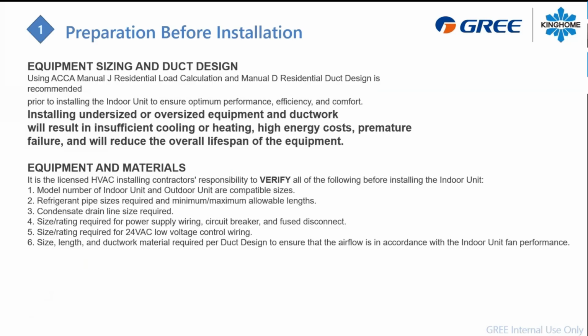So first things first, every time you do a job, make sure your ductwork and the equipment are compatible with your load calculation. This is according to the ACCA Manual J residential load calculation. You need to match a good load calculation from the house you're about to install the unit in. If it's undersized or oversized, it will not be efficient enough in cooling or in heating. And just be sure that you have the right ductwork, the right amount of CFM running through this unit.